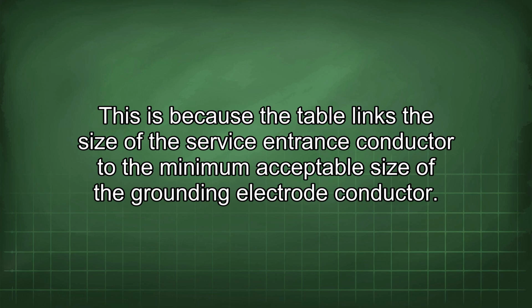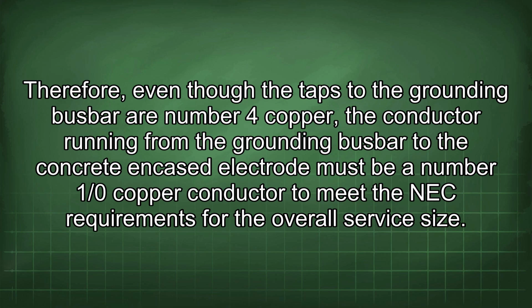This is because the table links the size of the service entrance conductor to the minimum acceptable size of the grounding electrode conductor. Therefore, even though the taps to the grounding busbar are number 4 copper, the conductor running from the grounding busbar to the concrete encased electrode must be a number 1/0 copper conductor to meet the NEC requirements for the overall service size.